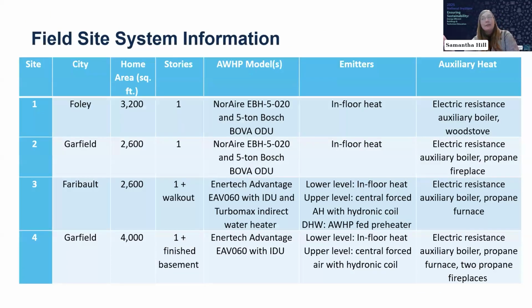To summarize what kind of air-to-water heat pumps we installed, we had 4 systems, 2 of which, the first 2, 1 and 2 in this table, were relatively simple systems. They were third-party split systems, so they had basically very simple controls. We happened to pair a coil-only air source heat pump with a NorAire air-to-water heat pump unit, and both of these homes had in-floor heat, meaning the emitter in these homes was a radiant slab. All sites also had auxiliary electric resistance boilers in case there were problems with the air-to-water heat pump or the air-to-water heat pump couldn't meet the entire heating load. And the first 2 sites didn't have any cooling and didn't have any domestic hot water. So those air-to-water heat pumps were just providing space heating.